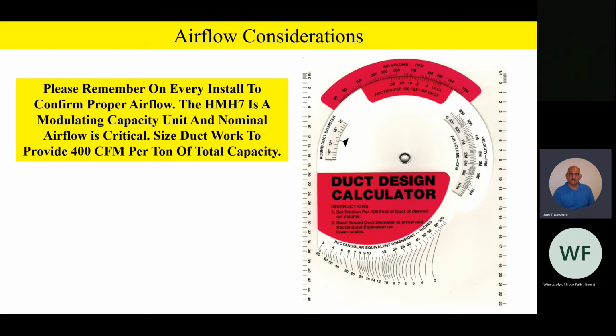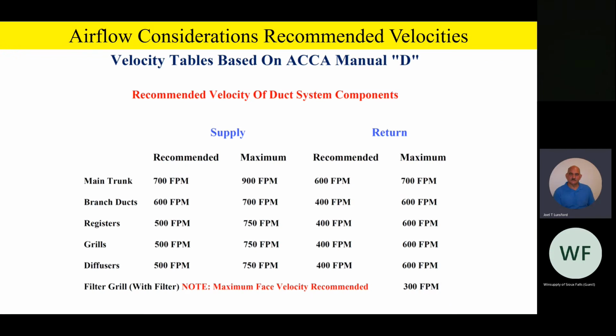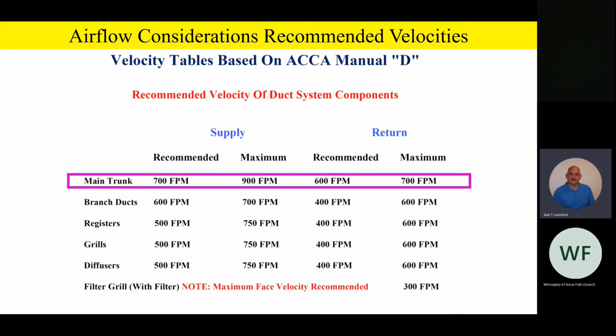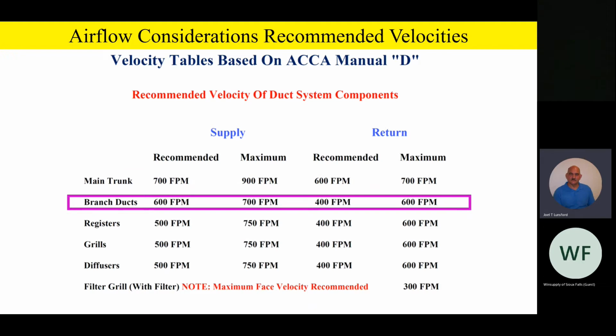In addition, as a quick reminder, the velocity tables that are in ACCA Manual D: be sure when you're building your duct systems or modifying your duct systems to try to go with your recommended velocities on your key components, like your main trunk. For instance, the recommended velocity is going to be 700 feet a minute on the supply, 600 feet a minute recommended on the return on those main trunks. Your branch runs are going to be 600 feet a minute on the supply, and 400 on the return recommended, and so on. So look at this table in Manual D. This is right out of Manual D. I'm not going to go over every single one, but you can read it yourself.